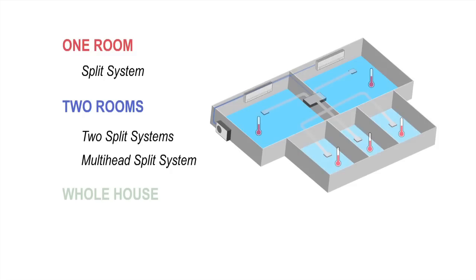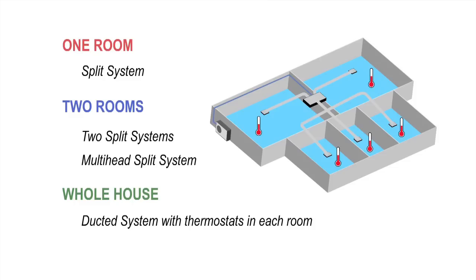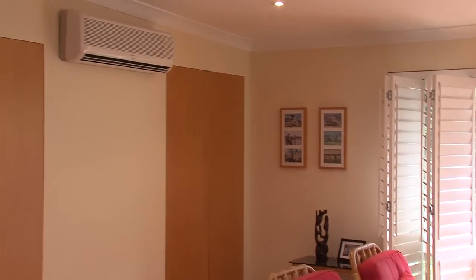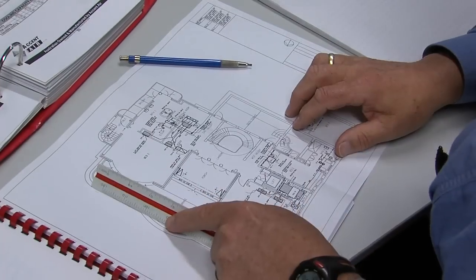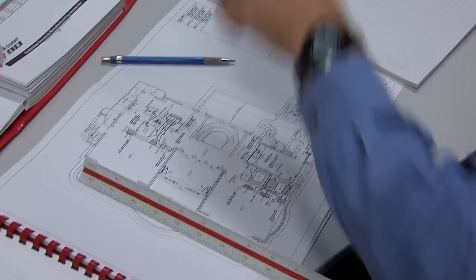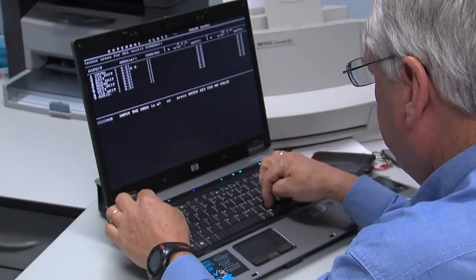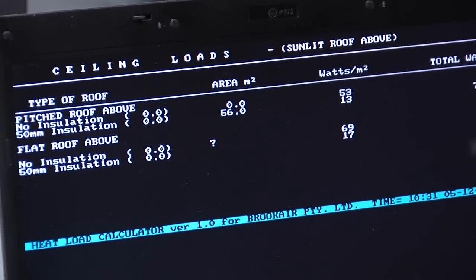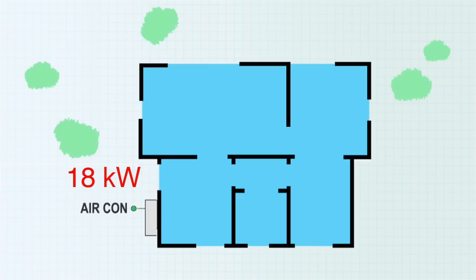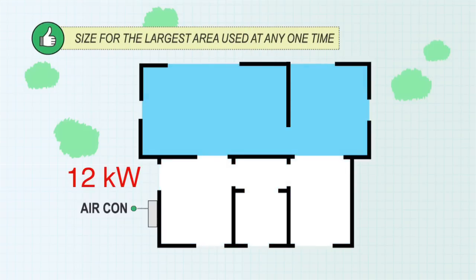For whole house conditioning, ducted systems which use thermostats in each room have superior efficiency and comfort over standard ducted systems. Correct sizing of air conditioners is critical. This must be based on the output capacity, usually in kilowatts, not horsepower or electrical input. Use a heat load calculator, which takes the thermal performance of the building into account. With ducted systems, don't size for the whole house — size for the largest area that will be cooled or heated at any one time.